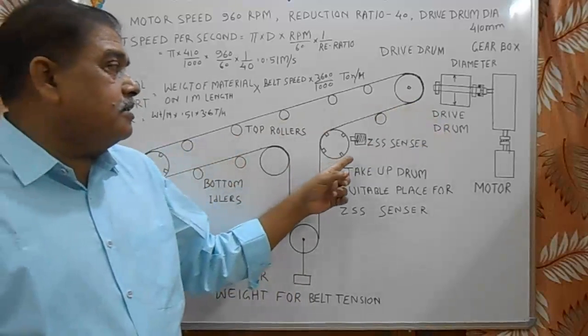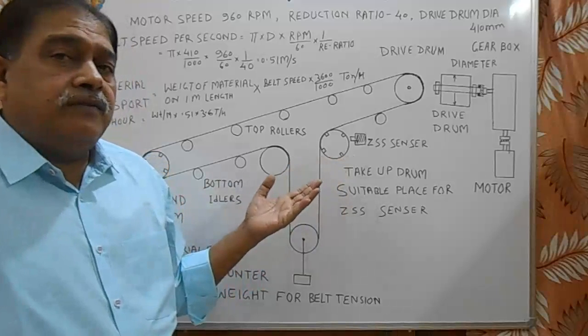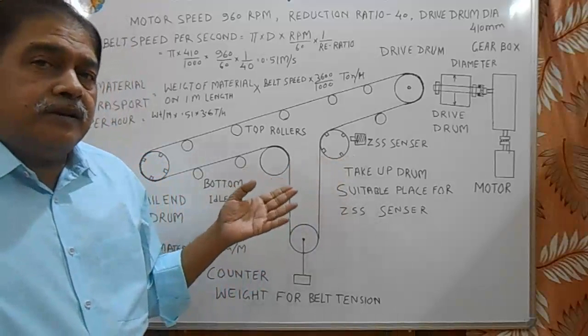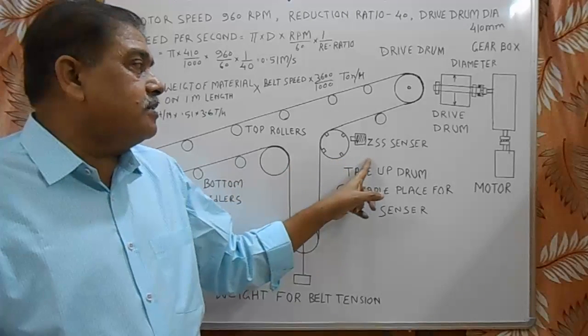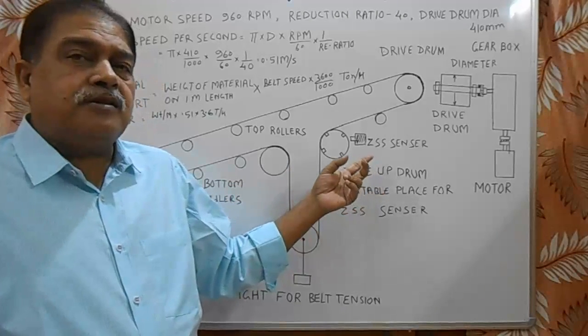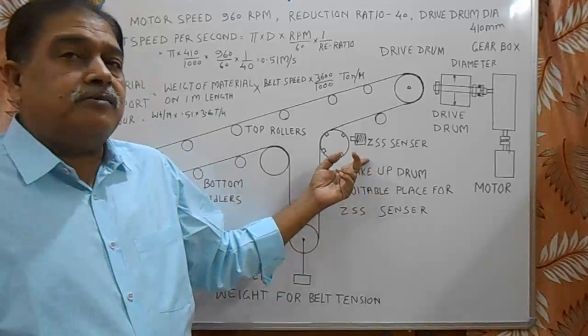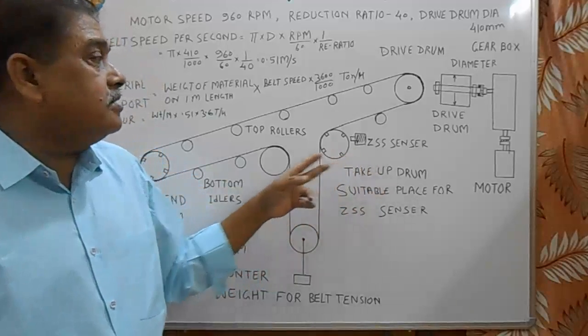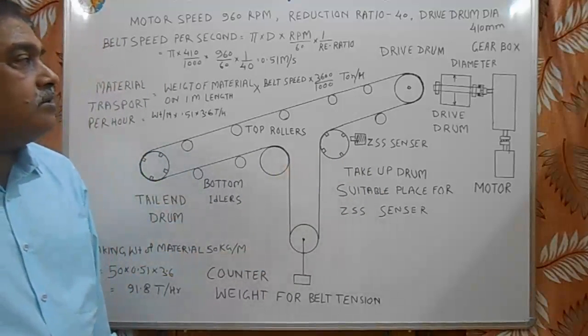This ZSS is used to sense speed of belt. Whenever the speed of belt decreases below 75% of speed, this ZSS gives a signal that belt speed is slow or belt is snapped out. In addition to these, various safety devices are also used in belt conveyor.